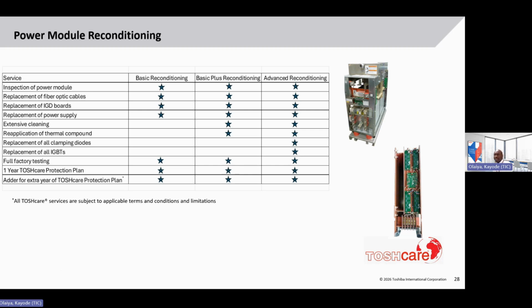The last slide here is a summary of what we're replacing for the three different levels of reconditioning. First, as mentioned, is the inspection of the module. We're replacing the fiber optic cables. If you remember, that's a key part of the power module. The IGD boards, these are the boards for turning the IGBTs on and off. They're connected directly to them. And these have electrolytic capacitors, which is why we replace them if the module has been on the shelf for a long time. We also replaced the power supply board. That's another board that has electrolytic capacitors. And then all the levels include the full factory testing, the 1-year protection plan, and the option to extend that for a second year. So that's the basic.